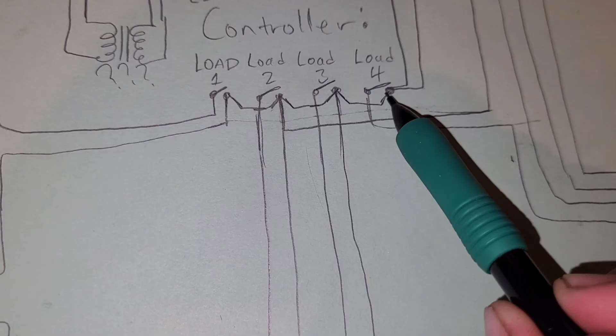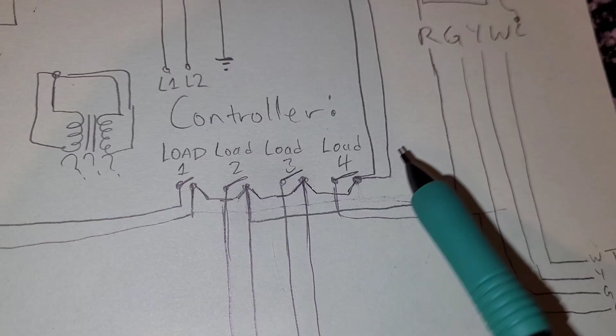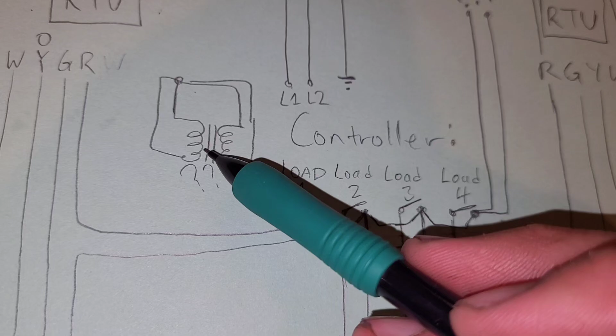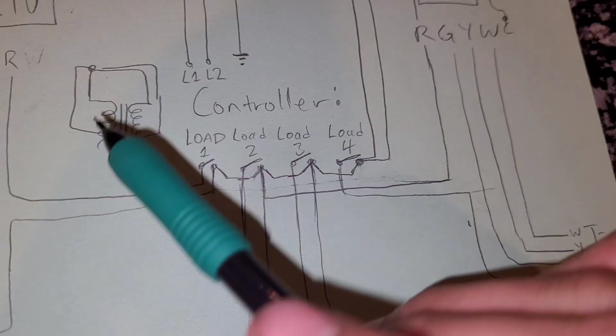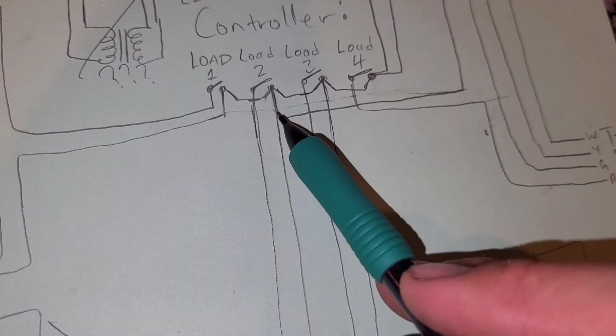And then on load 4 they had these 2 random wires that actually went nowhere. They just dead-ended, tied in right here, so it's kind of unnecessary to have those hooked up. And they had this 24 volt transformer with everything just wire nutted, kind of making it extra messy in there. So we just got rid of this, removed the jumpers, moved this wire from here over to here, and we were good.